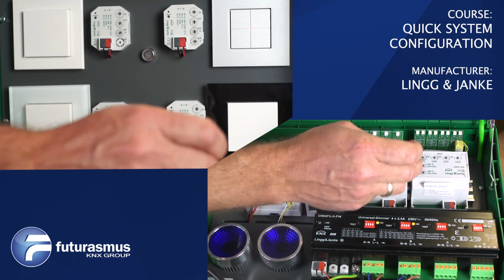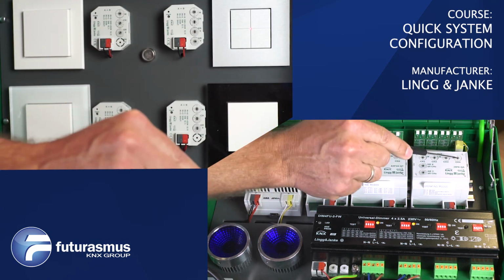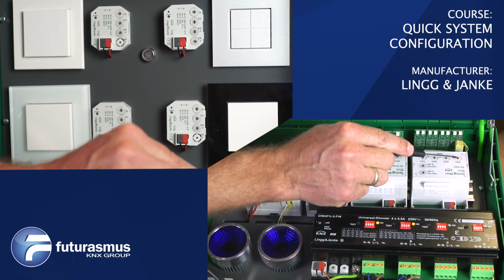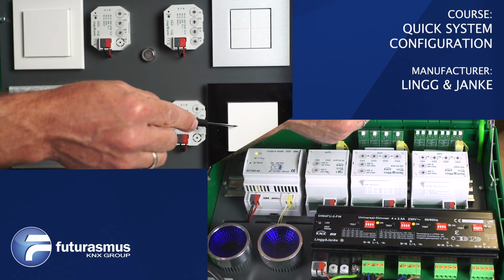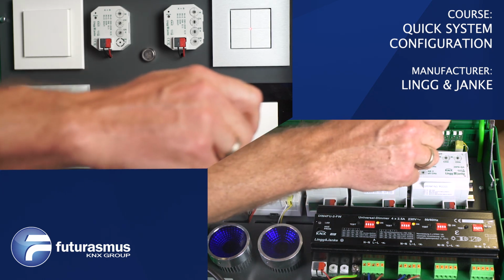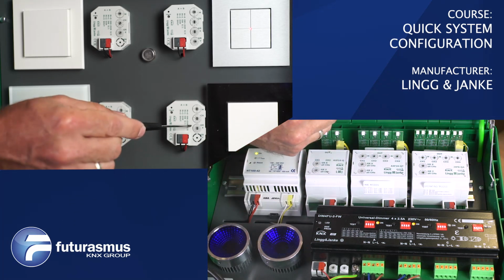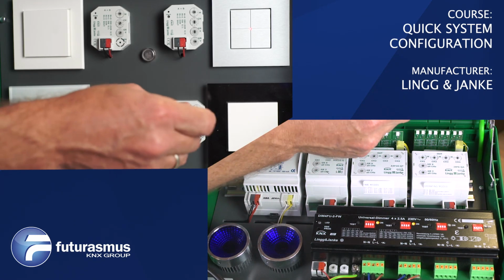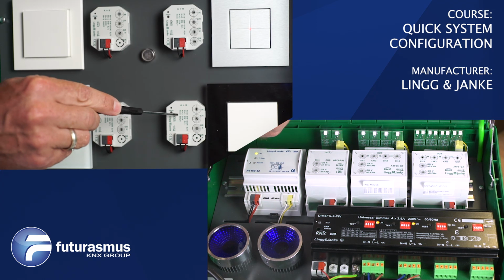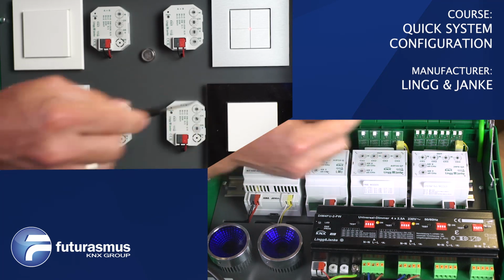So let's say it's a shutter, and let's say we want to configure, for instance, channel 4. So we put this on a shutter. Operation shutter is without slats, so just going up and down. So we put it on 2. Now we need to configure the push button and the channel in the actuator still. So let's say the channel, let's put it to something different. Let's say 8, for instance, just to be different. Now 8 here, we connect now this one to channel 4, because we want to control channel 4. Obviously we need to set the type of switching we want to do, and we want to do a shutter switching. So we will have to set this on the value 3.